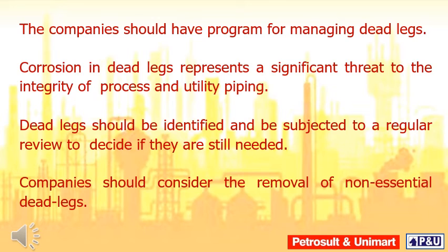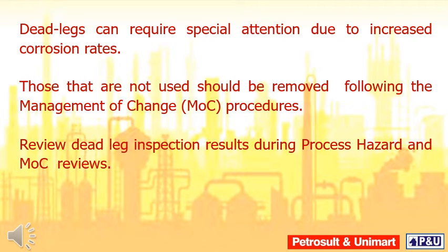Companies should have a program for managing dead legs. Corrosion in dead legs represents a significant threat to the integrity of process and utility piping. Dead legs should be identified and subjected to a regular review to decide if they are still needed. Companies should consider the removal of non-essential dead legs. Those that are not used should be removed following the management of change procedures.